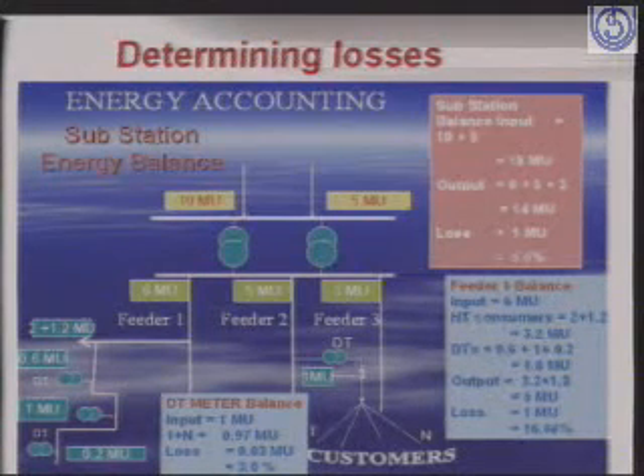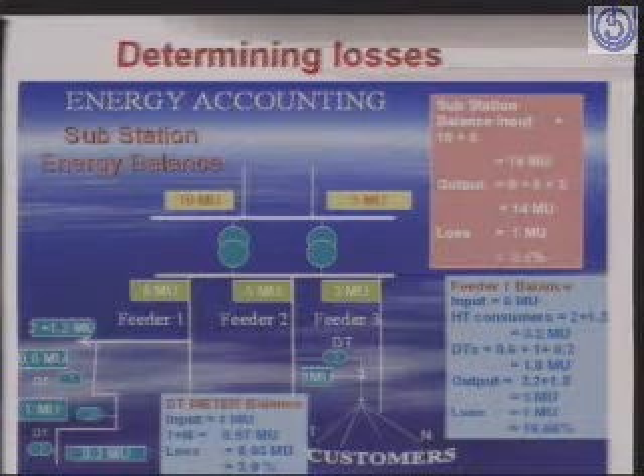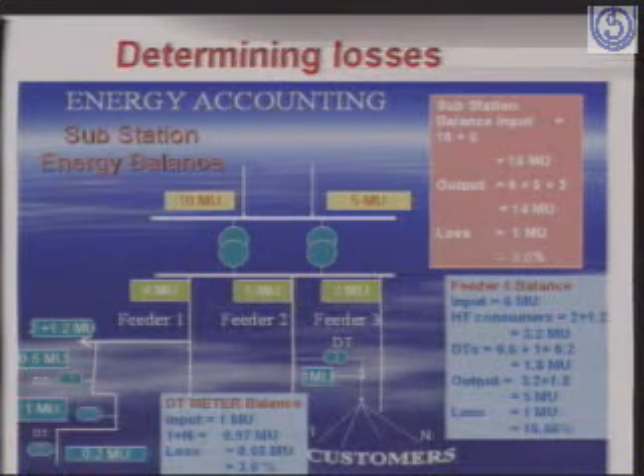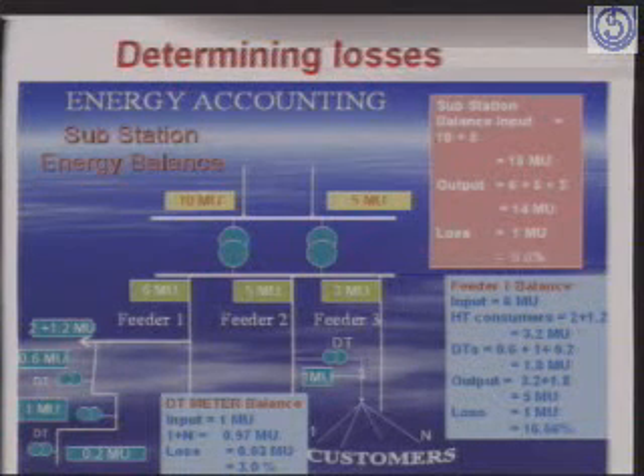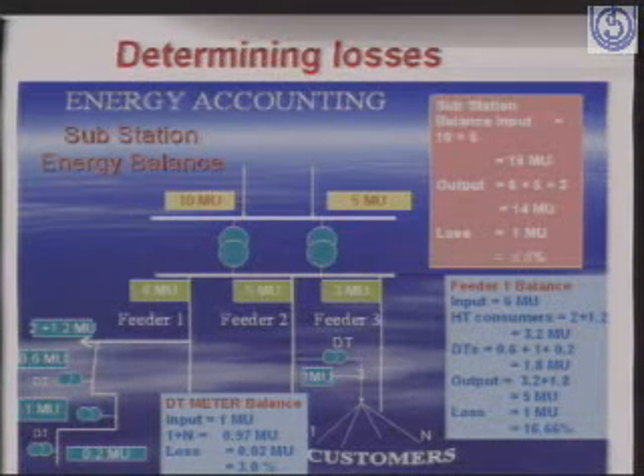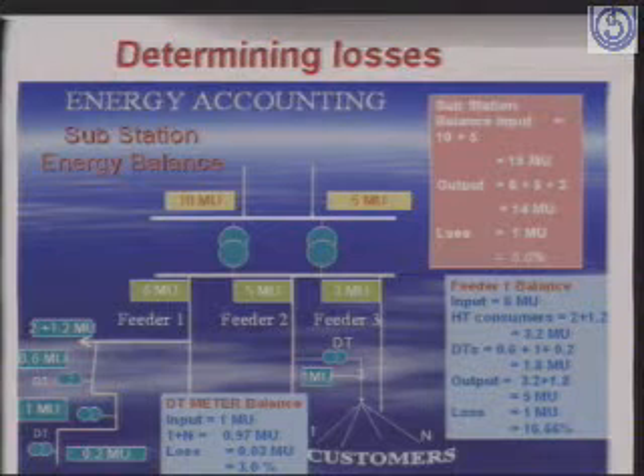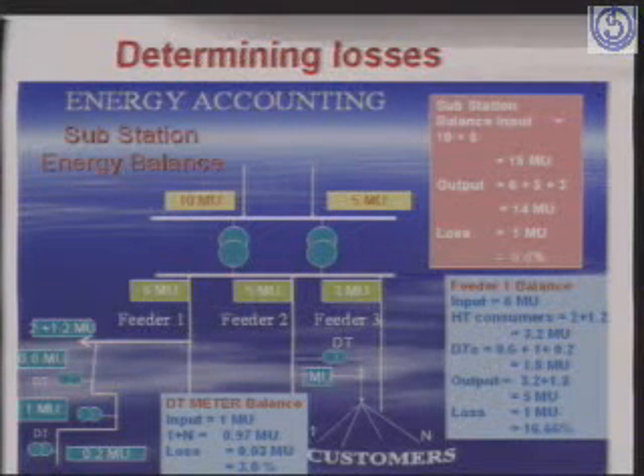This chart, which is very well explained in your course books, briefly explains how the energy flows and how the overall losses are estimated. In this particular case, the substation is receiving 15 million units, output is 14 million units, so we have a loss of 1 million unit, which comes out to 6.6% of dispatch. Then we have 3 feeders, and feeder 1, there are 2 HT feeders which are going out and through which we are sending 2 million units and 1.2 million units.